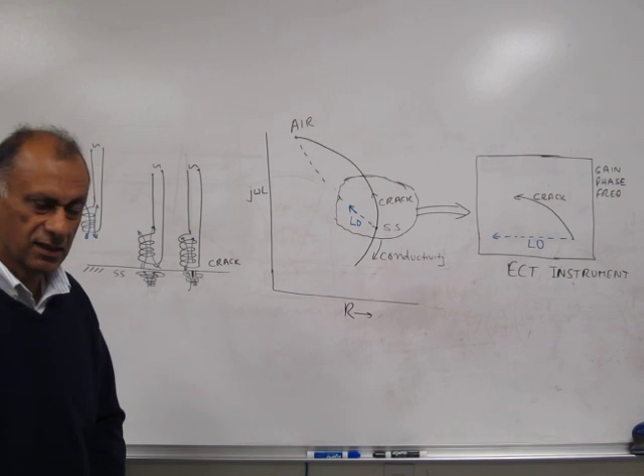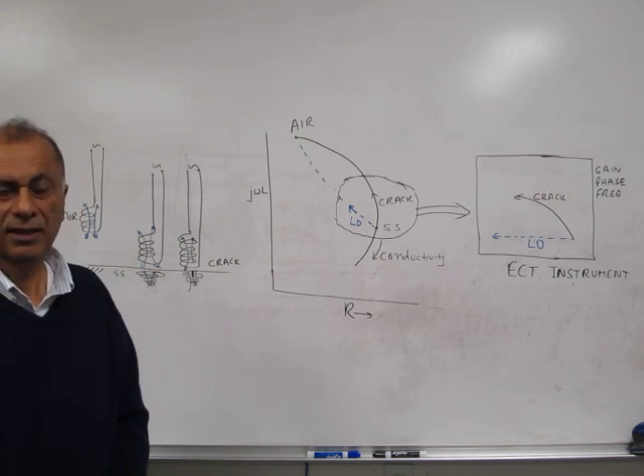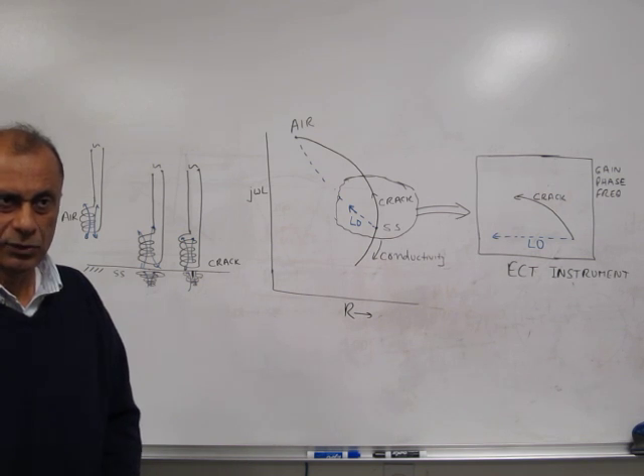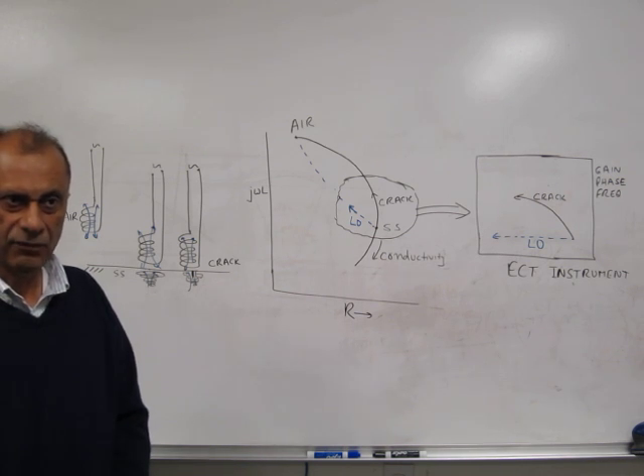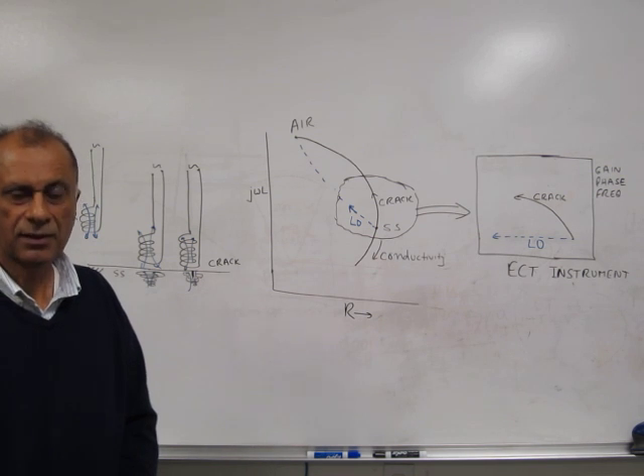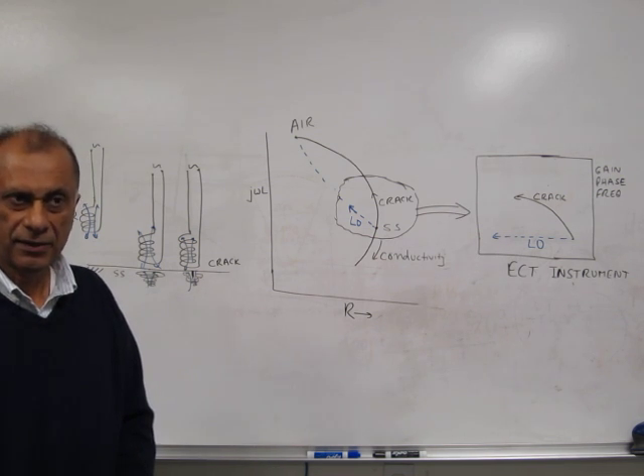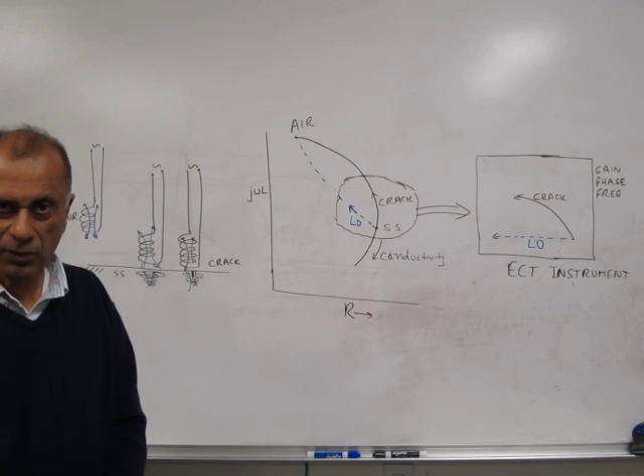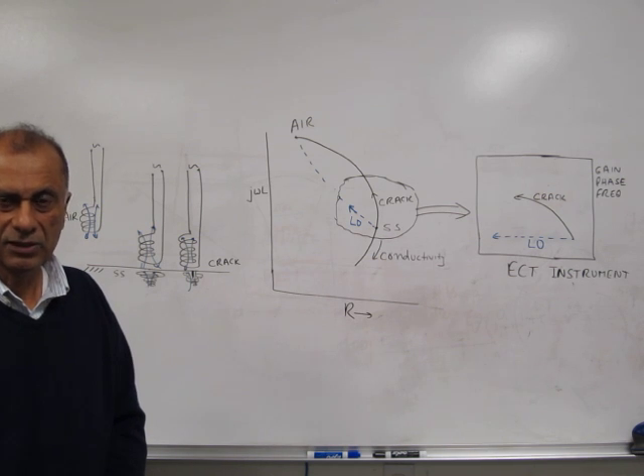Here I will be discussing the principle of eddy current testing. Eddy current testing uses a coil which produces a magnetic field and which is lowered onto the surface of a conductive material. Because of the alternating magnetic field in the coil, eddy currents are produced inside that material, which oppose the magnetic field of the coil, thereby changing the impedance of the coil.